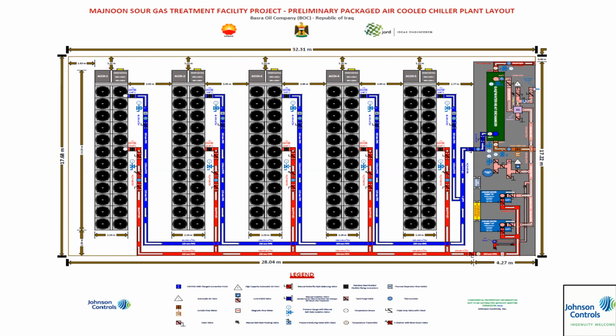Must have been a challenge to deal with all that sand in the environment. You'd be surprised. But yeah, that is an issue. We do have to factor that in. There's a derate factor for it. So in this case, we need to maintain a little over 3 meters, which is about 10 feet roughly, between the units so that these condenser fans aren't fighting for the same heat rejection. You get head pressure problems. But the actual distance in a normal application is only 8 feet. Because of the sand potential, we add another 2 feet to it.